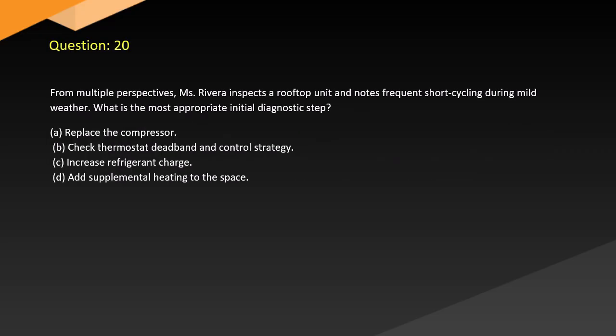Question 20. From multiple perspectives, Rivera inspects a rooftop unit and notes frequent short cycling during mild weather. What is the most appropriate initial diagnostic step? A. Replace the compressor. B. Check thermostat deadband and control strategy. C. Increase refrigerant charge. D. Add supplemental heating to the space.